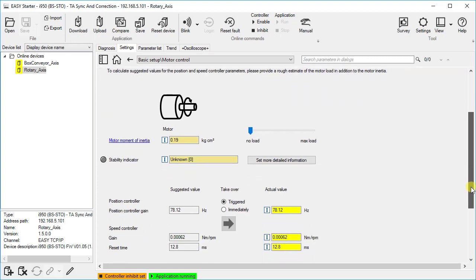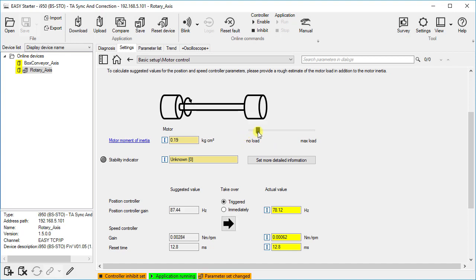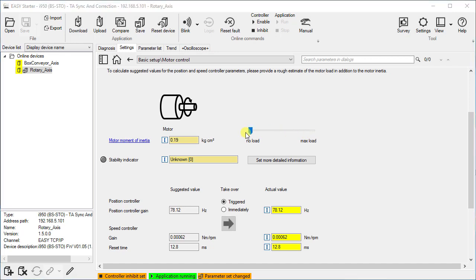The challenge is to adjust both controllers optimally at the same time, speed control loop and position control loop. For the adjustment of the most important controller parameter, the gain, we can use the slider control. By moving the slider to the right, an additional load is added to the motor inertia. For each load mass inertia, the required gain of speed controller and position controller is automatically suggested. The suggested values can be triggered via the button or immediately accepted and tested. In addition, the state of stability is marked for enabled controller.